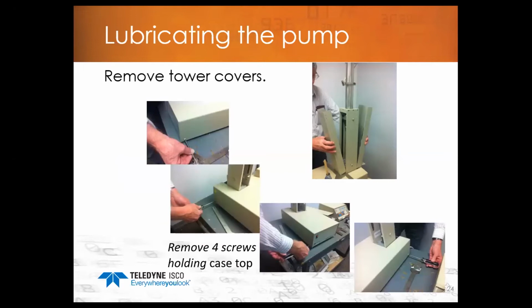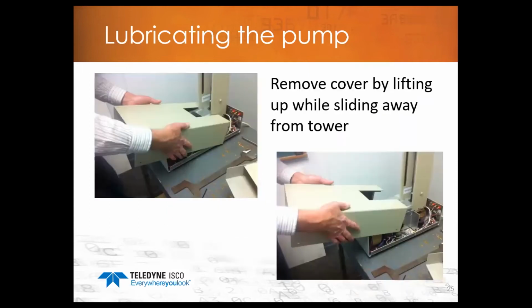The next step would be to go ahead and remove the case bottom cover of the pump. The older pumps have 4 screws. Our newer pumps have 6. So depending on the age of your pump, you'll either be removing 4 or 6 case bottom screws to access the inside of the unit where the lubrication wheel is at. And then, with everything removed as far as your screws, you can go ahead and remove the case bottom cover.